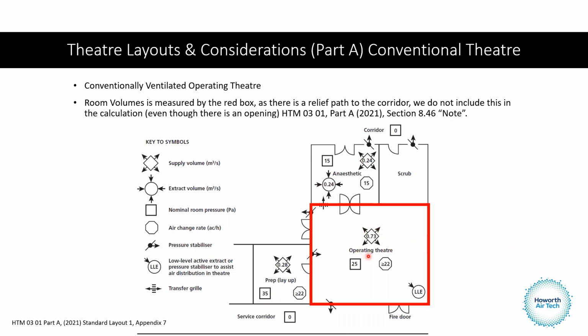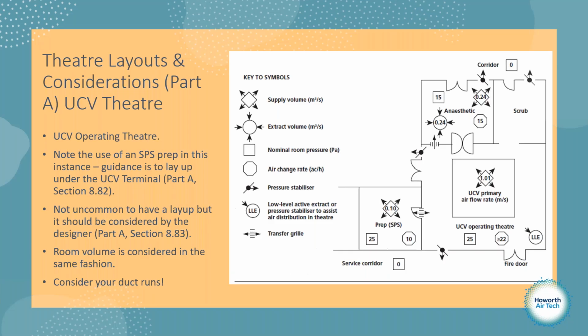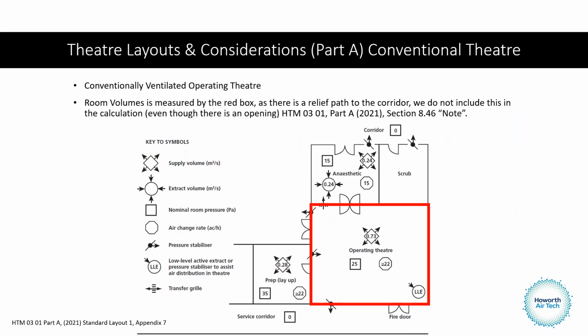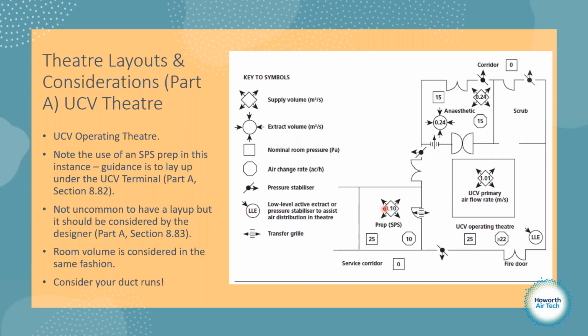So before I move to the next slide, conventional theatre, layup prep. We now put a canopy in the room and it makes things slightly different. Again, this is a standard layout from the HTM. We measure the room volume in exactly the same fashion, so there's no concerns there. But notice that this clean space over here has now turned into a sterile pack store, an SPS. The volume in the room has dropped considerably, so that's gone from 280 litres to 100 litres.